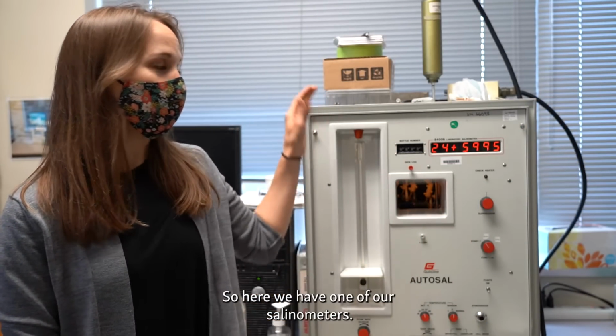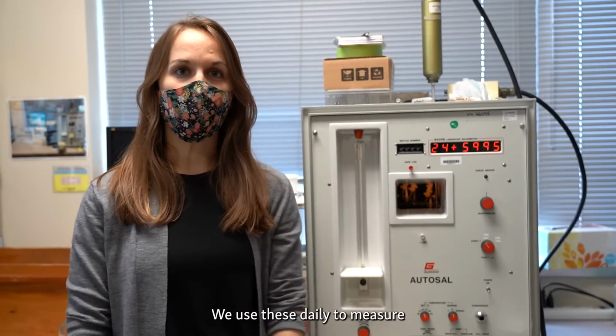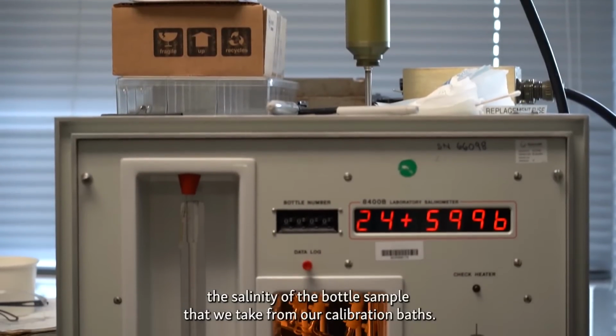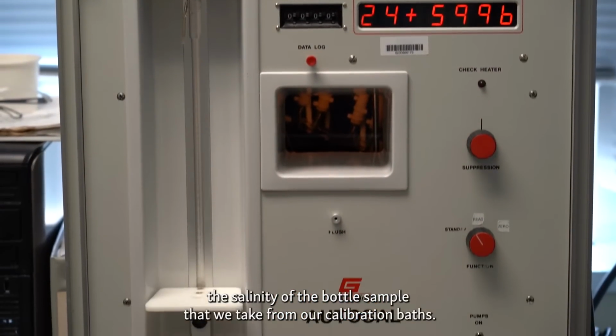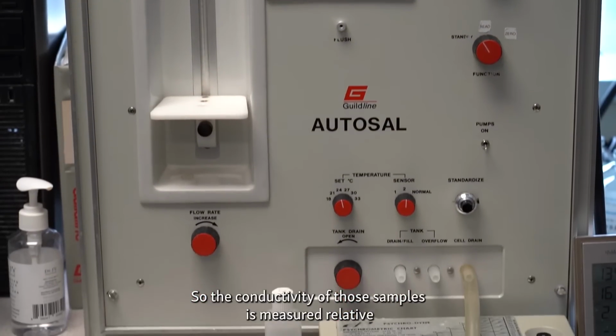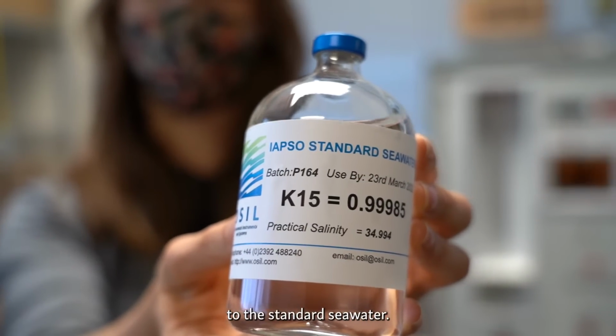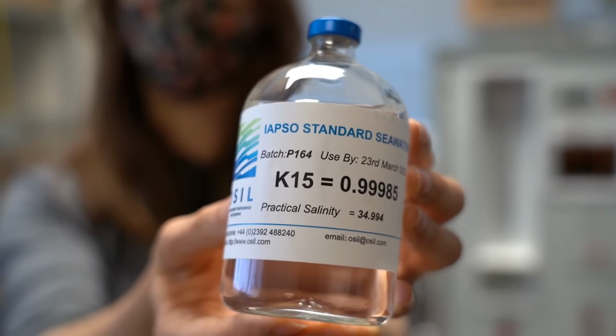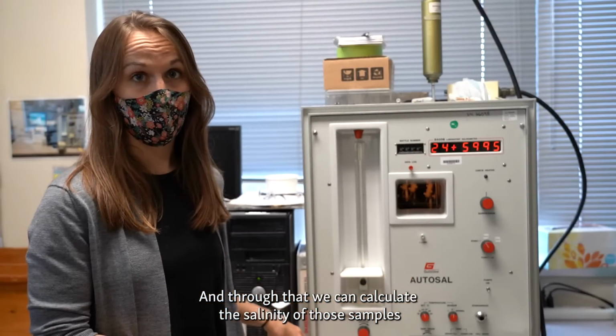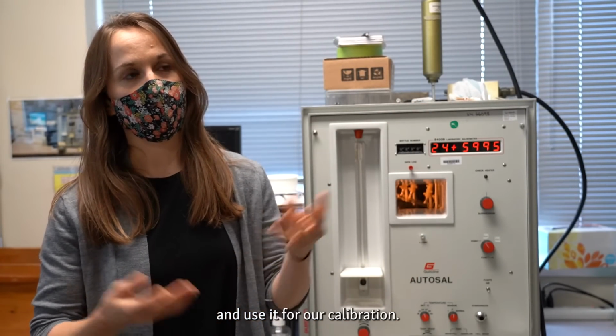Okay, so here we have one of our autosalinometers. We use this daily to measure the salinity of the bottle samples that we take from our calibration baths. So the conductivity of those samples is measured relative to standard seawater, and through that we can calculate the salinity of those samples and use it for our calibration.